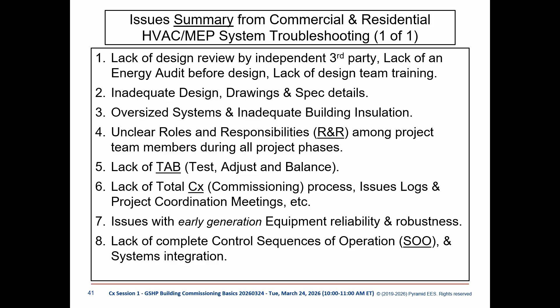Lack of a complete control sequence of operation - this is the devil here. You really need to nail this in bullet items, not long run-on paragraphs that are all uppercase. It has to be bullet items, clearly defined and reviewed by multiple project team members, because whatever you put in this sequence will not be programmed correctly from day one - I can assure you that. It's not going to happen. You have to go through an iterative process, test it, make sure your sequence is actually working as intended. So those are just examples here.